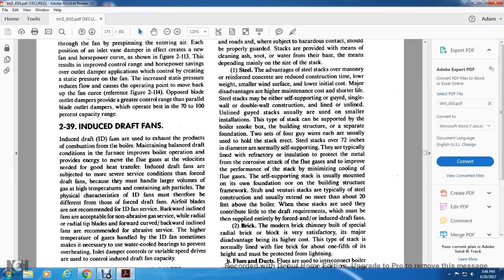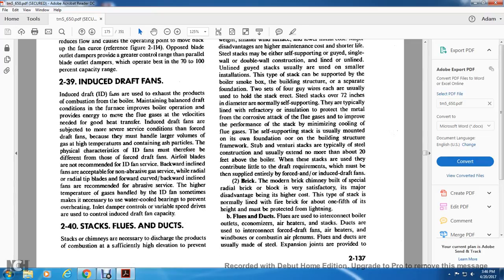A self-supporting stack is usually mounted on a foundation and or the building structure framework. Stubs and venturi stacks are typically of steel construction and usually extend no more than 20 feet above the boiler. When such stacks are used, they contribute little to the draft requirements, which must then be supplied entirely by forced or induced draft fans. Brick. The modern brick chimney, built of special radial brick and block, is very satisfactory, its major disadvantage being its higher cost. This type of stack, normally lined with fire brick for about one-fifth of its height, must be protected from lightning.